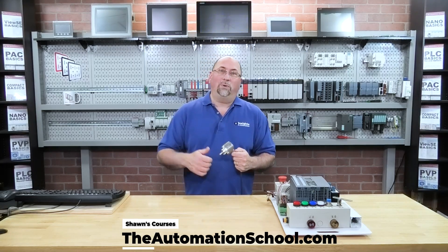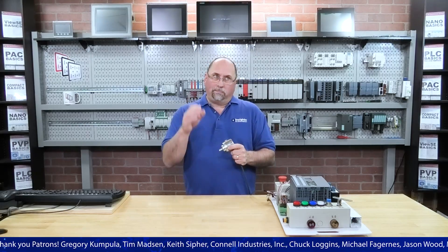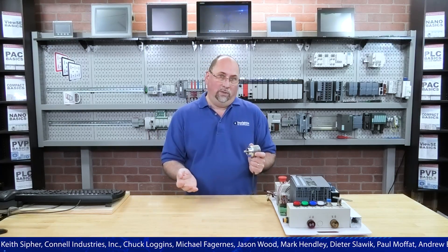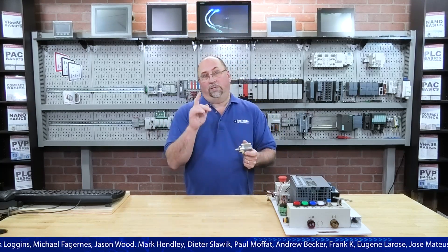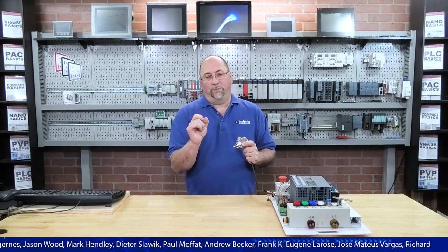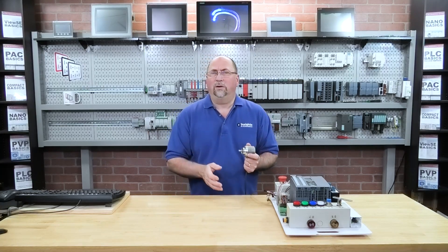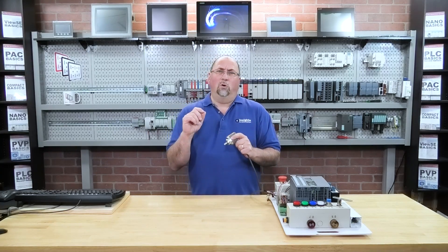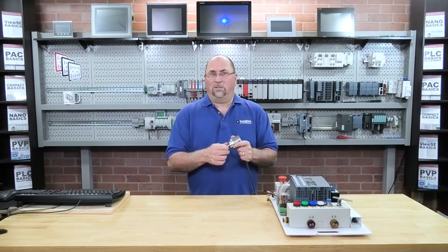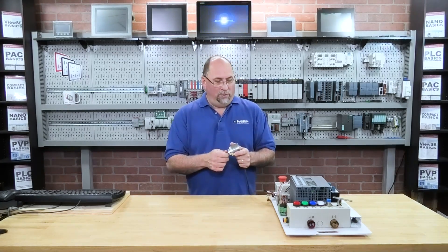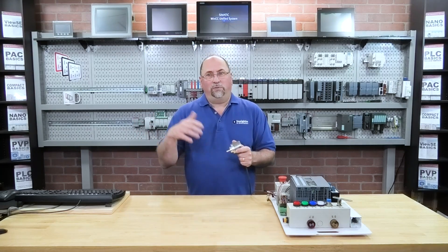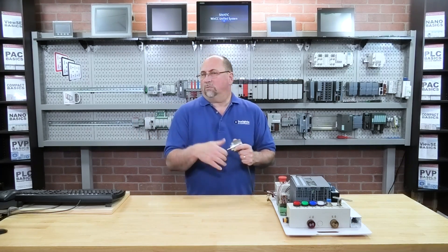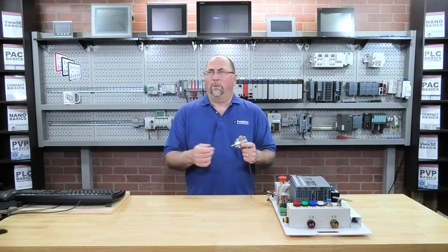So really that's how easy it is to use the high speed counter in an S7-1500 compact using that technology object. There really wasn't much to it. There was a few different steps here. We had to enable the high speed counter. We had to make sure we had the right IO points that we were using, they had to match the high speed counter. When we did the technology object, we wanted to change it because by default it was pulse and direction, and we wanted to change it to encoder. So we have to do that. And I did also change the speed, the delay on the inputs, so there's no delay. So we'll get the fastest speed possible.